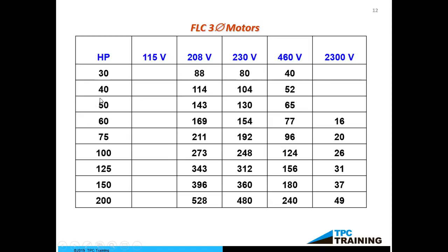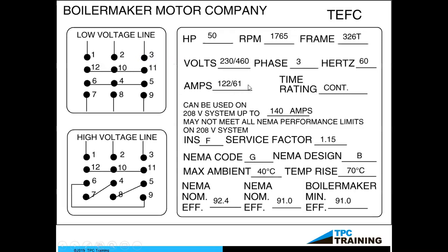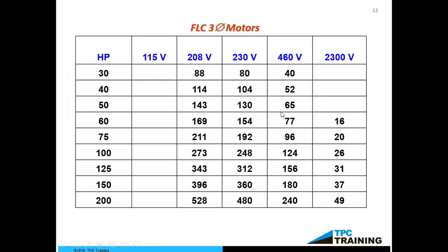So if we come to our 50 horsepower motor and we come over to 460 volts, we can see the number is 65. It's close. Over here we had 61, but this number over here will always be higher. And we have to use this number, this 65, to choose our wire size for the motor, to choose, let's say, our disconnect, to choose our overcurrent protection, whether it be an inverse time breaker or time delay fuses. We have to use the FLC. What we would use the FLA for would be to choose our overload protection.